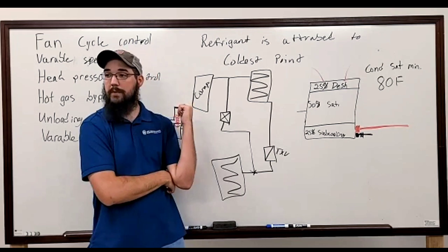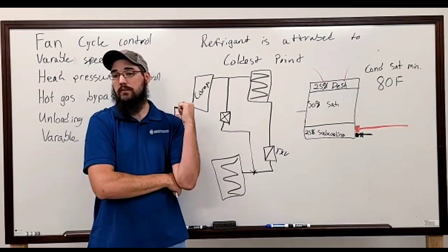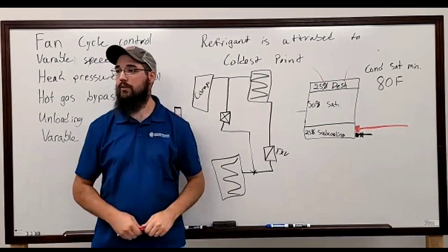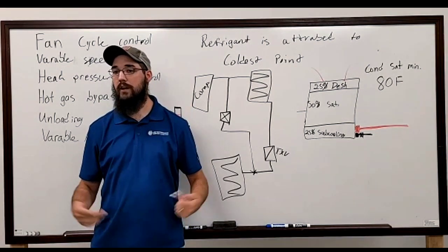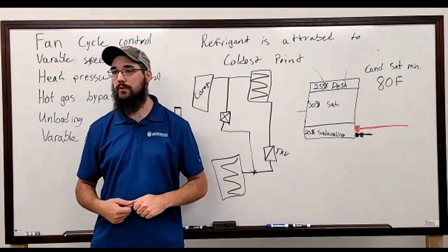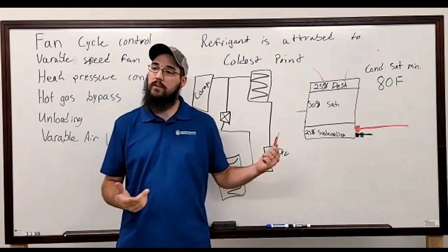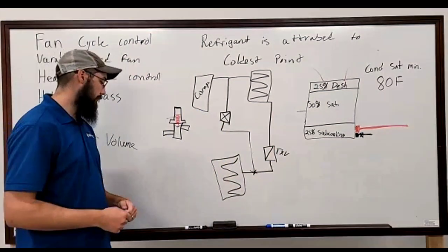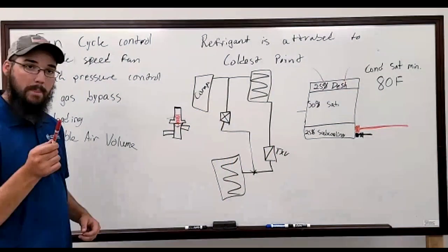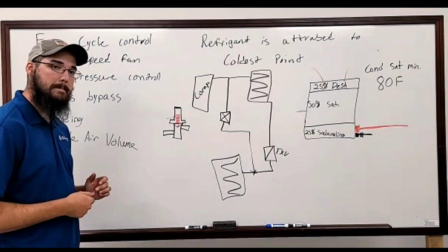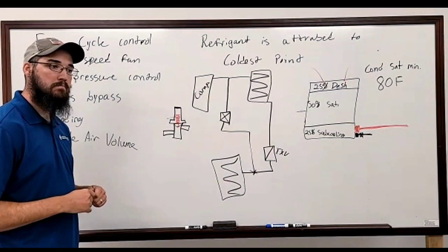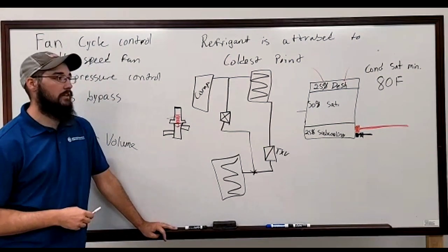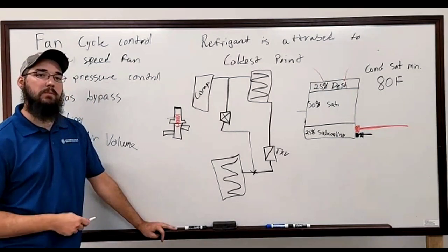But like I said, you grab that pipe. If the pipe is hot, it's flowing discharge. If it ain't hot, it's not being used. On a 90-degree day, I wouldn't expect it to be used. 70, 65, yeah, it might be. Anyway, basically, you would grab them the same way.